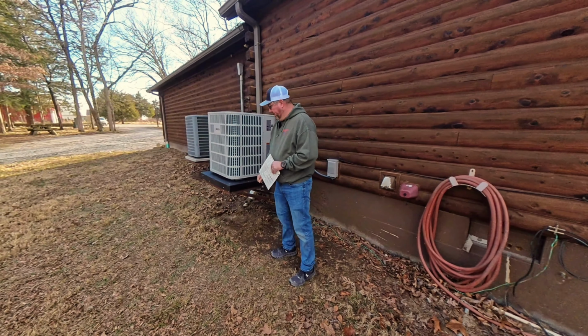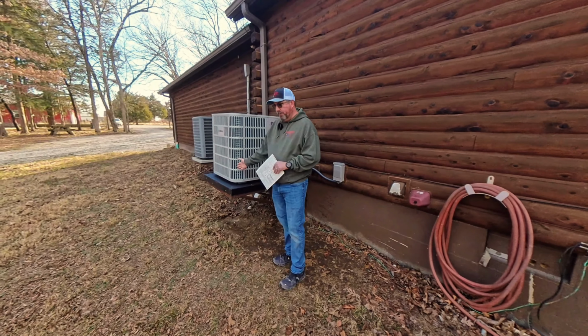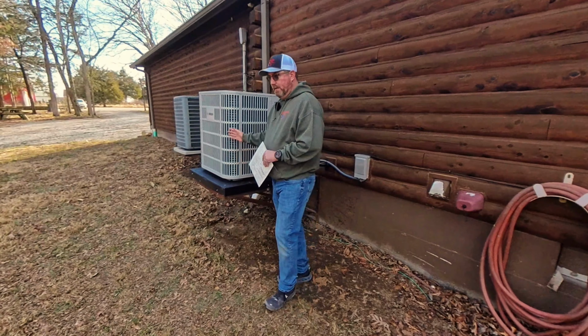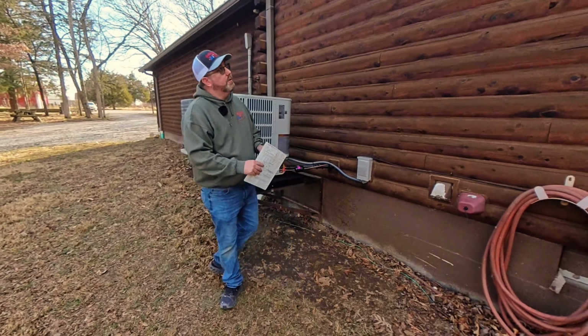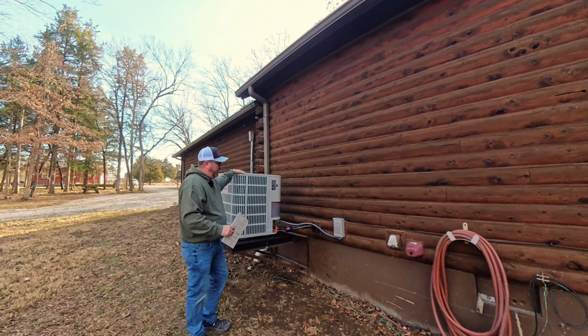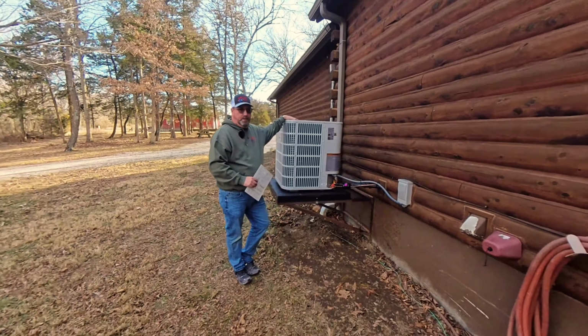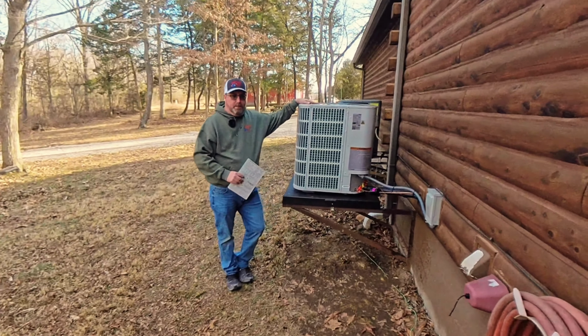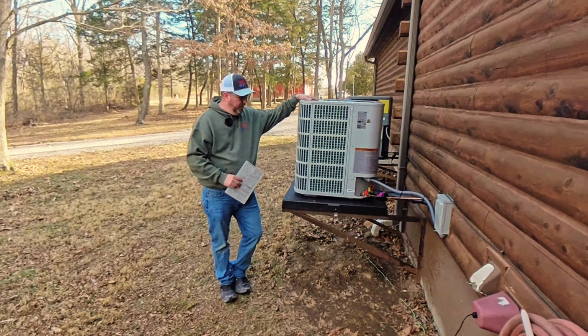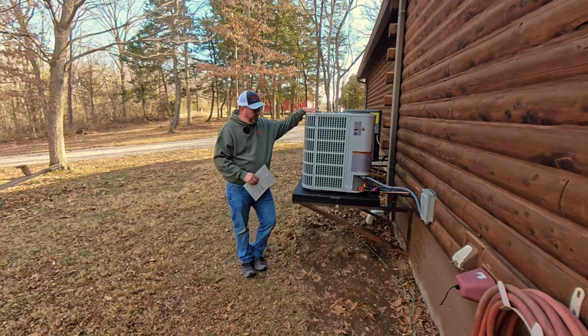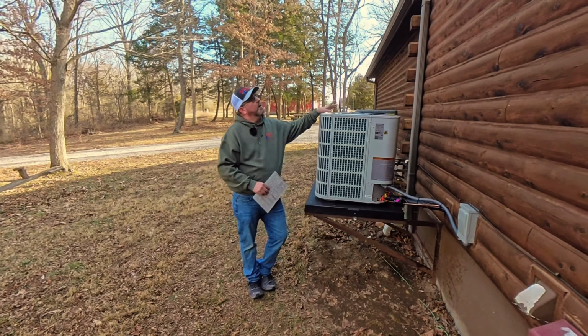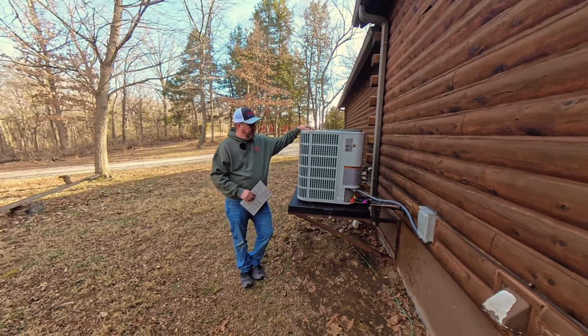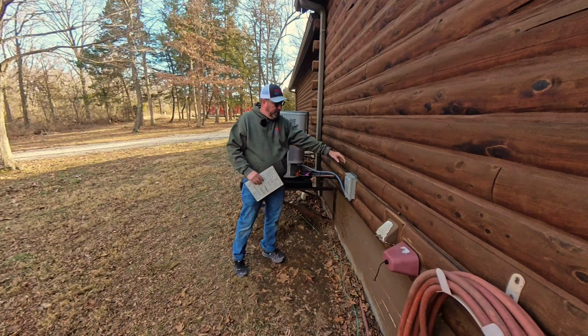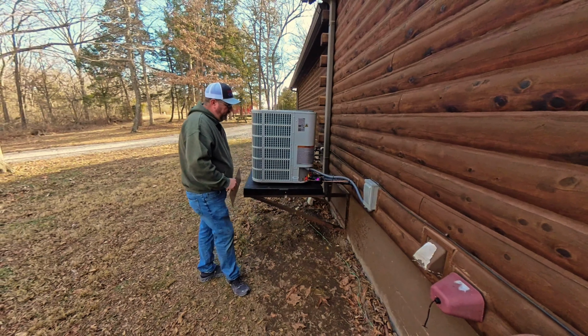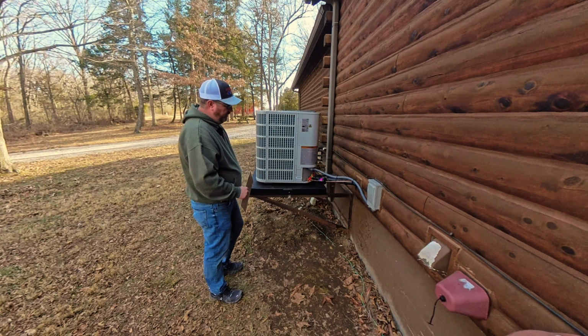The homeowner wanted to keep it, so we can only get the unit so far out away from the house. We would typically like to see this unit out a little farther due to the gutter line and not having anything drop on the unit coming off of the roof. Unfortunately, we could not get that out farther without putting it on the ground on a pad and moving it away from the house a little farther. Homeowner is aware of that, and he's been noted to keep an eye on that. We do put a surge protector disconnect on these to help protect those components. Something else to note with maintenance in the future.